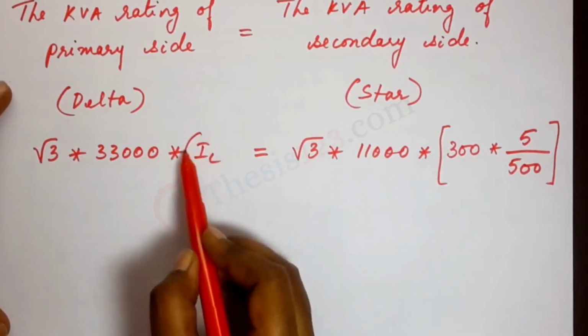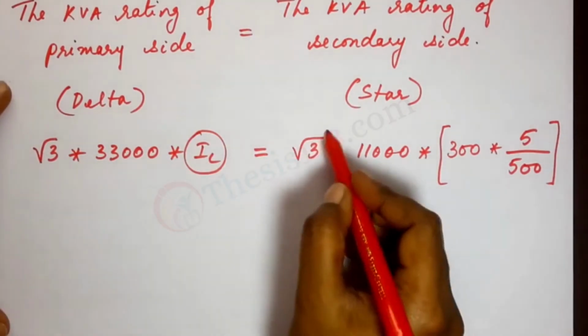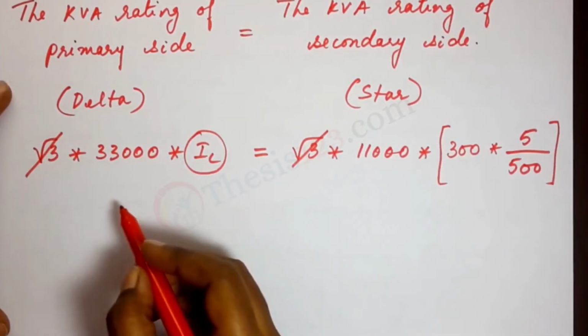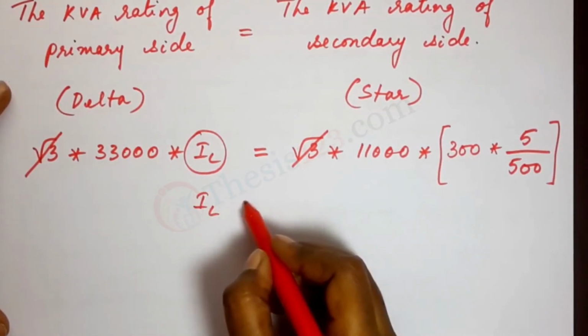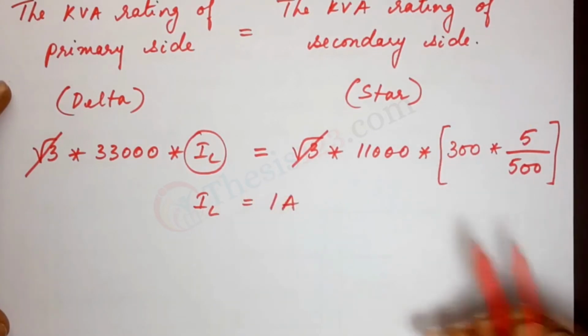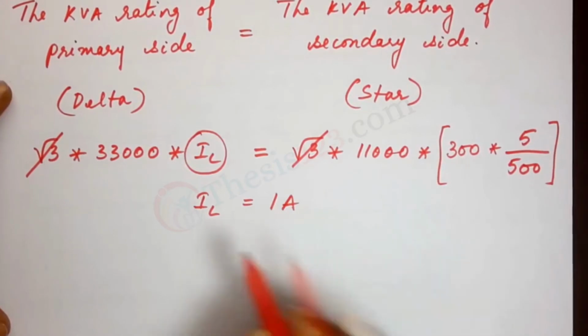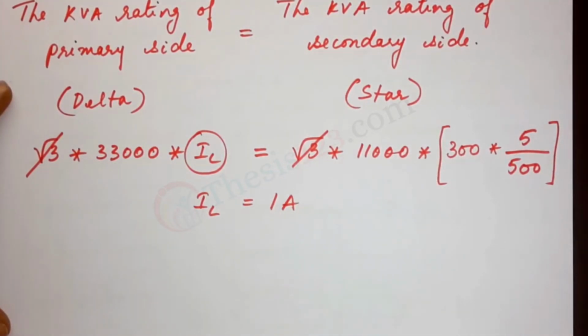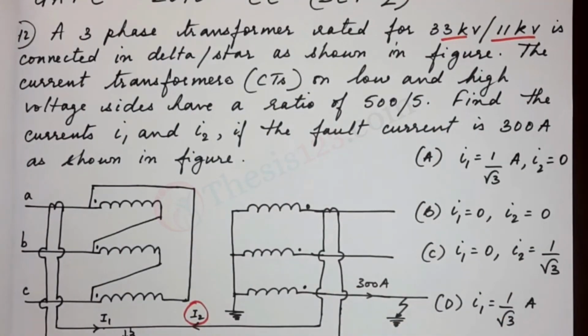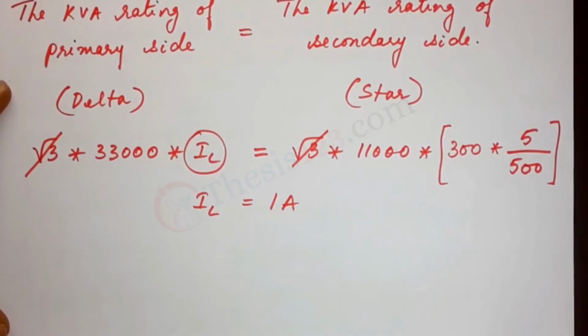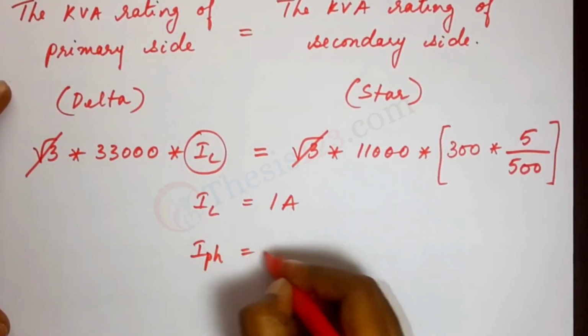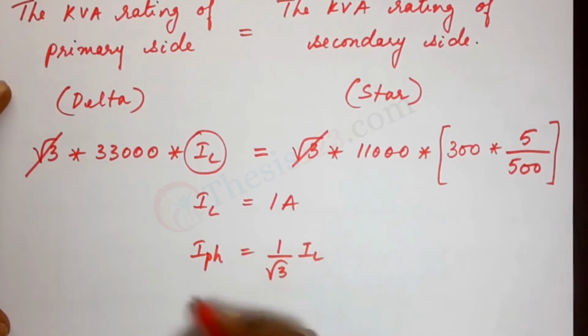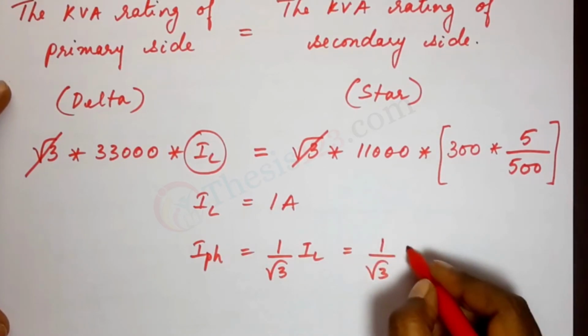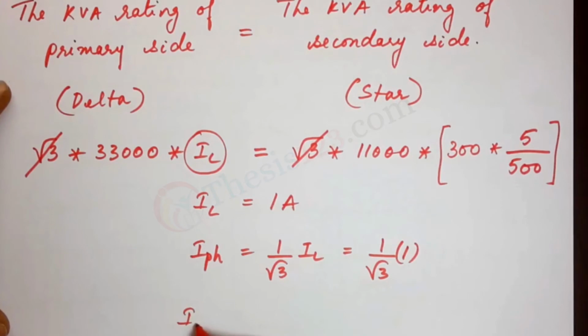Now when you solve this, you should get the value for the line current. Root 3 can cancel out and you can do a whole lot here. You should have the value of line current as 1 amp. Everything cancels out really. So IL equals 1 ampere. Now we need the phase current because we are finding out IL from the primary side and that's the delta connection. Be very careful with the line and phase though, okay? So I phase equals 1 by root 3 times IL. IL is 1 amp, so 1 by root 3 times 1 ampere. So we have our value of I1. I1 equals 1 by root 3 ampere.